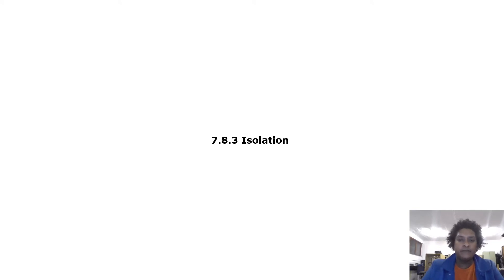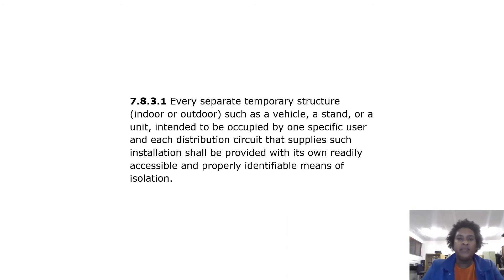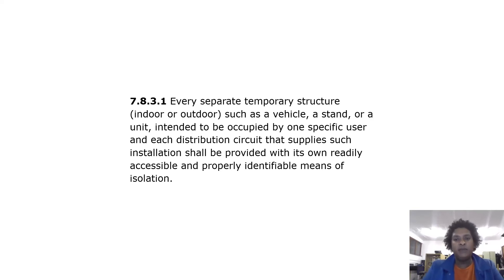Isolation: every separate temporary structure, indoor or outdoor, such as a vehicle, a stand, or a unit intended to be occupied by one specific user, and each distribution circuit that supplies such installations, shall be provided with its own readily accessible and properly identifiable means of isolation.